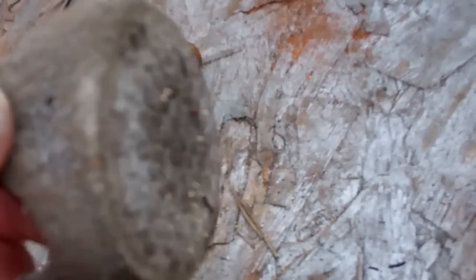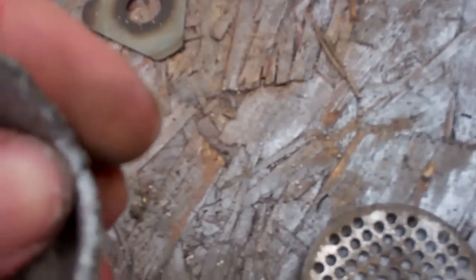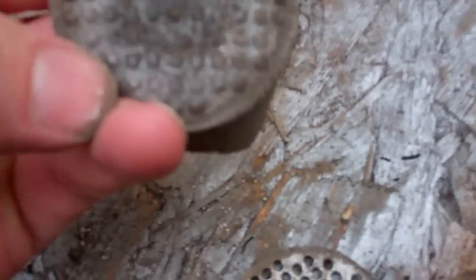That's probably what's blocked up - that looks quite muddy. That almost looks like it's melted, so it could have been some sparks from the grinder, I suppose. In the centre there you can see it looks very dusty and muddy. Probably copper oxide and debris from when it was installed.